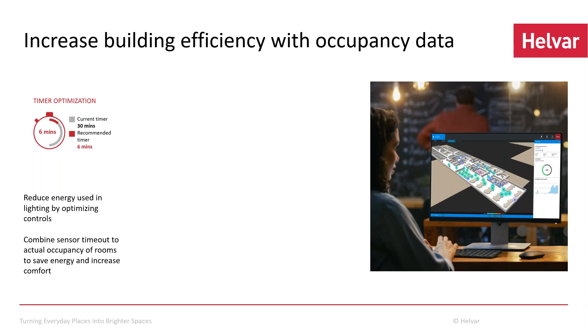In our example here, the sensor setting says 30 minutes, so the lights stay on for 30 minutes after the last trigger. But based on our occupancy data, we can say that in this space 6 minutes would be enough and would still give people the right amount of comfort. So this setting can be changed from 30 to 6, and if that's done, the user—the FM company, the owner, the tenant—saves energy in their lighting.